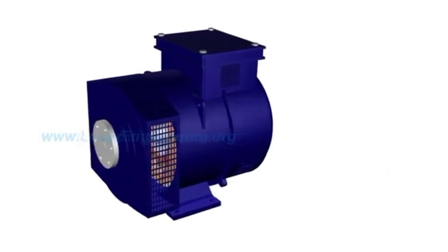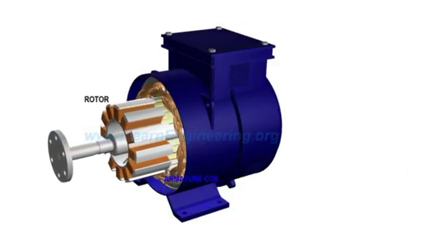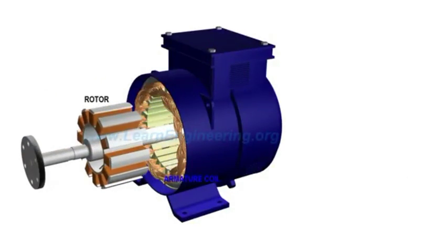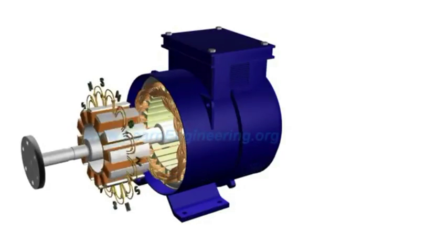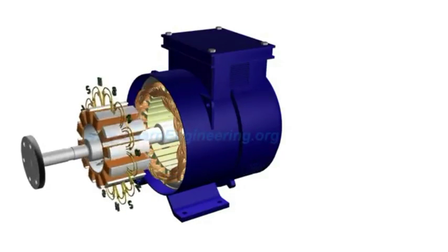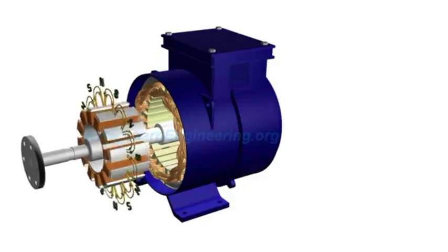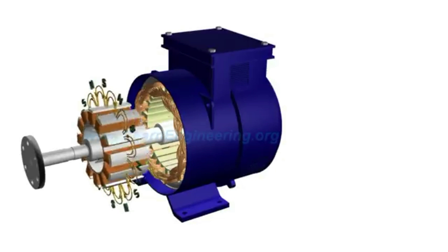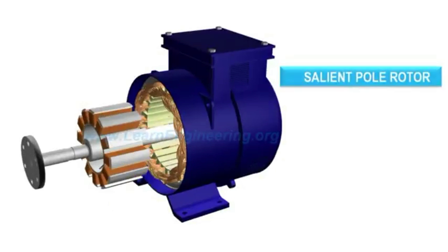Rotor and armature coils are the two main parts of an alternator. Rotor produces a rotating magnetic flux. Armature coils are stationary. And rotating magnetic flux associated with the rotor induces electricity in the armature coils. This kind of rotor shown here is known as a salient pole rotor.